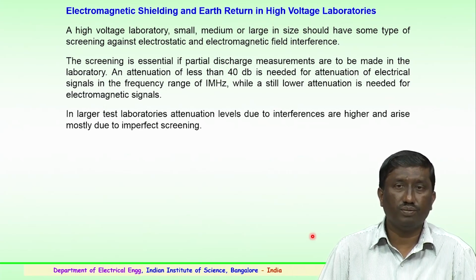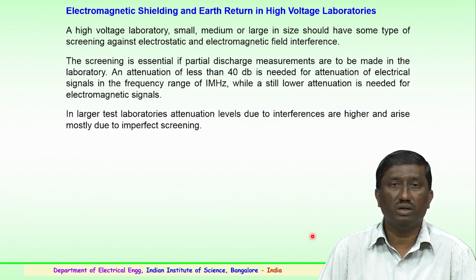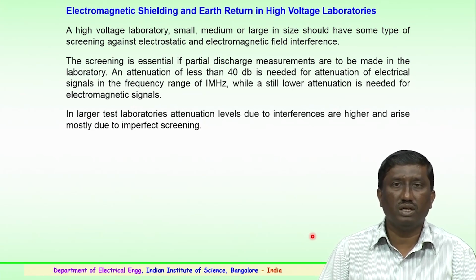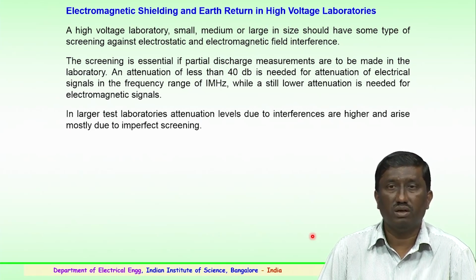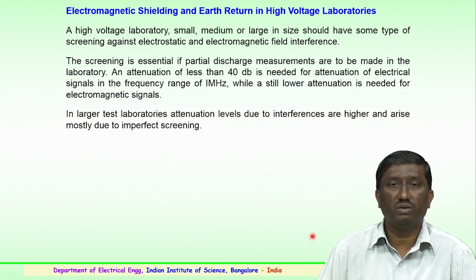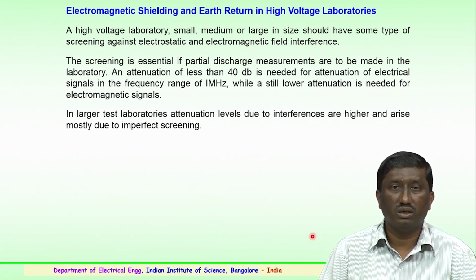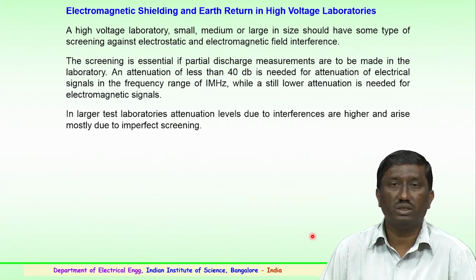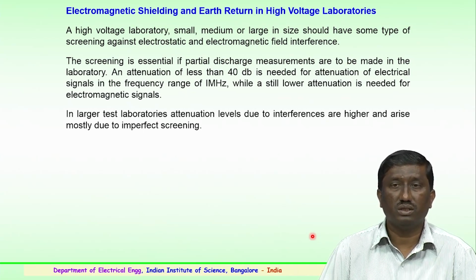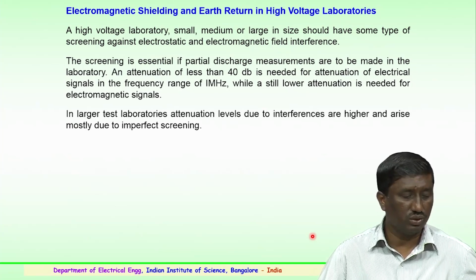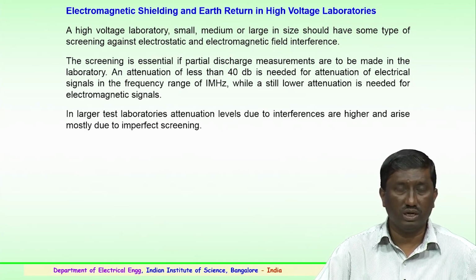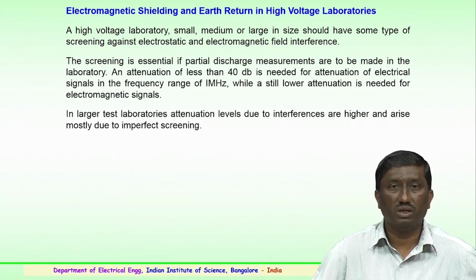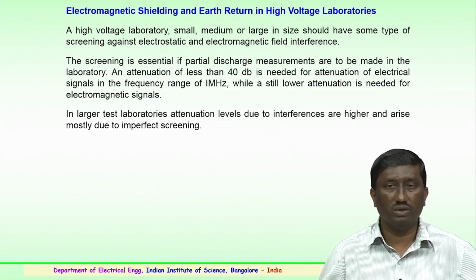So, the screening is essential if partial discharge measurements are being made in the laboratory. Here, an attenuation of less than 40, or much less than this value, is needed for electrical signals in the frequency range of 1 megahertz, while a still lower attenuation is needed for the electromagnetic signals. For large test laboratories, the attenuation levels due to interference are higher and arise mostly due to imperfect screening. So, the importance is to see that the entire laboratory is properly shielded and no interference is seen or observed during the testing of the equipment.